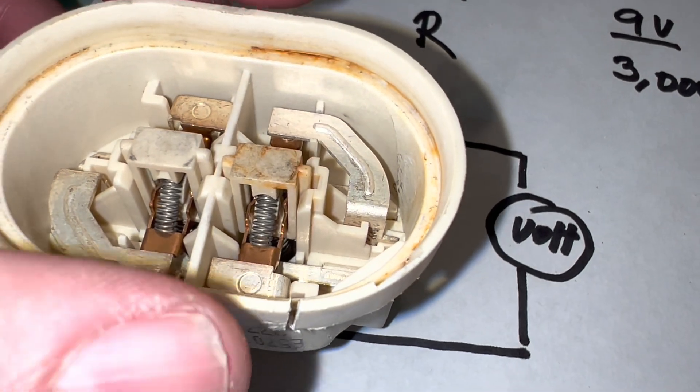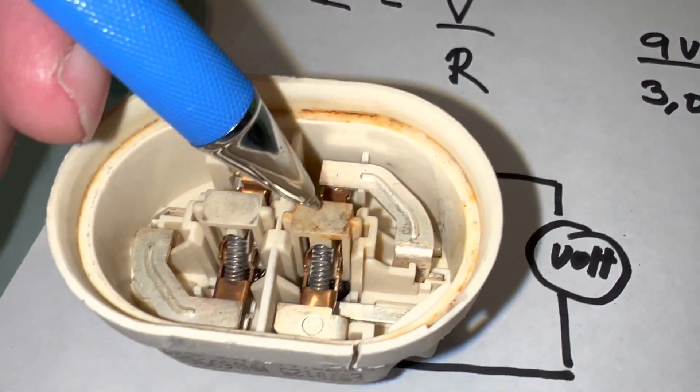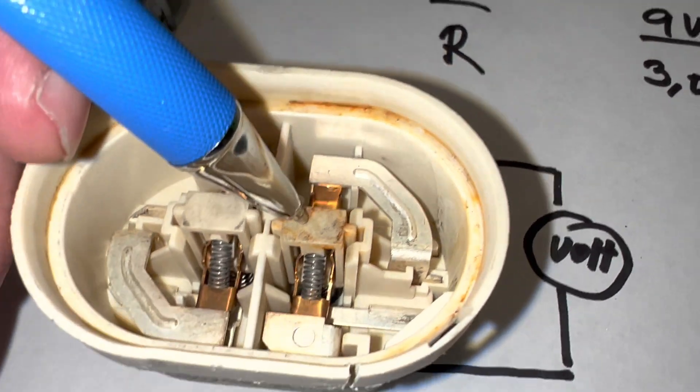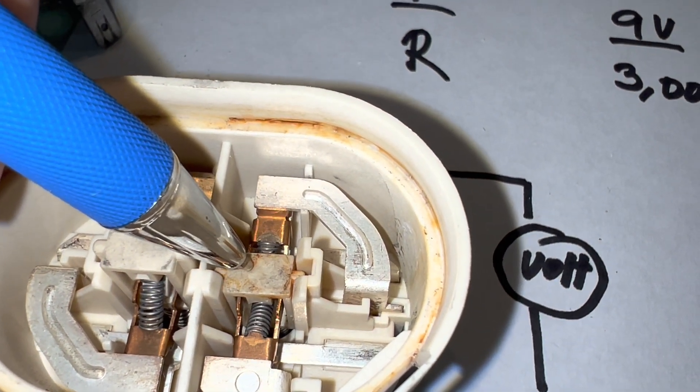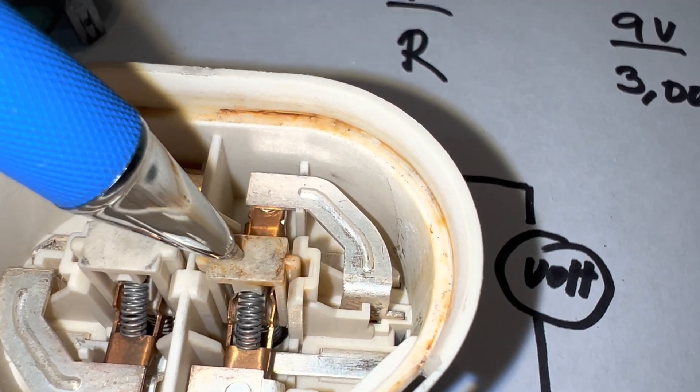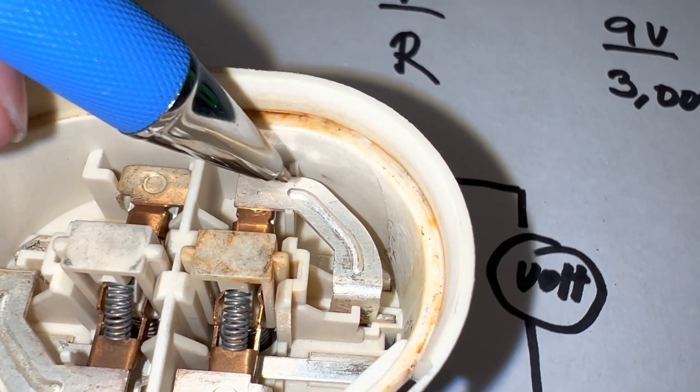Now when the water pressure comes in, it keeps pushing on the spring, and at one point it's going to cause it to flip. See the flip right there? And it's going to make contact with this middle terminal.